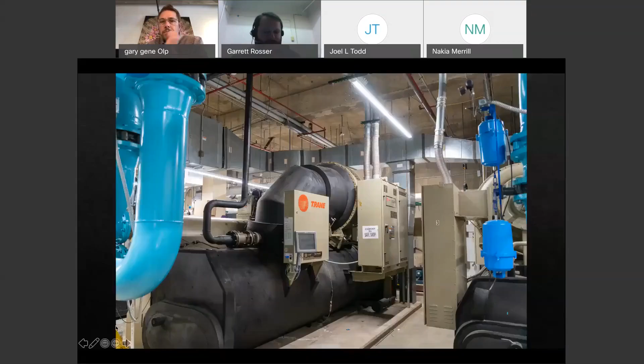These machines have served us well, and the technology has really come a long way. It opens the door for more refined responses in terms of central plant optimization, where we can look at variable flow on the secondary side, primary flow, and even variable condenser water flow. Trane has a great engineering newsletter on the subject of variable plant flow.